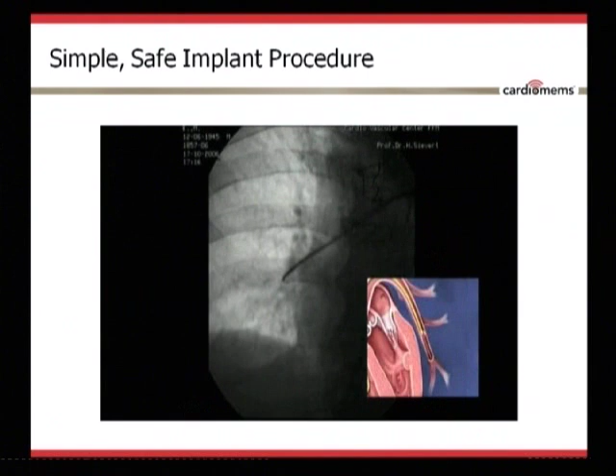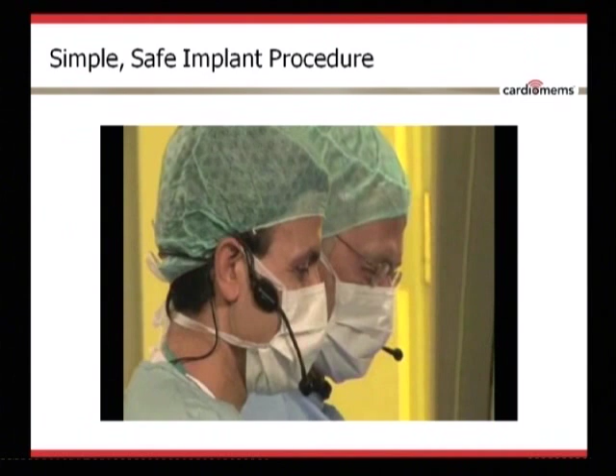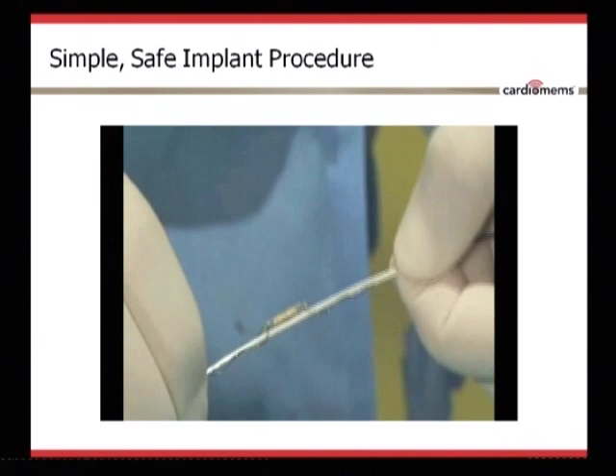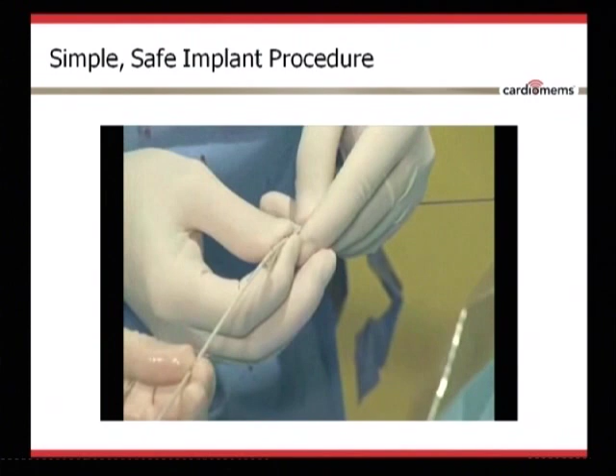An 035 guide wire is advanced through the Swan-Ganz catheter across the implant site. The Swan-Ganz catheter is removed while the guide wire position is maintained. The sensor is loaded on an over-the-wire delivery catheter. It is retained on the shaft by a nitinol tether wire which threads through the catheter shaft and through the sensor. The sensor delivery catheter is loaded over the guide wire.